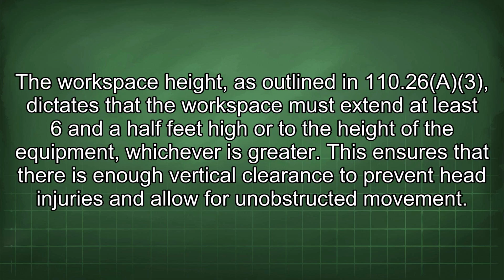The workspace height, as outlined in 110.26(A)(3), dictates that the workspace must extend at least 6.5 feet high or to the height of the equipment, whichever is greater. This ensures that there is enough vertical clearance to prevent head injuries and allow for unobstructed movement.